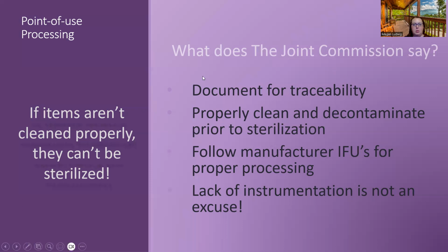The Joint Commission also makes you document anything you've used for point of use processing, your IUSS. So if you put it in that steam sterilizer, there will be a log that you have to fill out to go with that. And it's for traceability. If something comes back, maybe the machine failed the load or it didn't complete the load, something happened and it didn't process properly, they have that trace that you could follow to that patient. And the other way, if the patient got an SSI, surgical site infection, they could go back and do a little investigation to see what may have happened throughout the case.